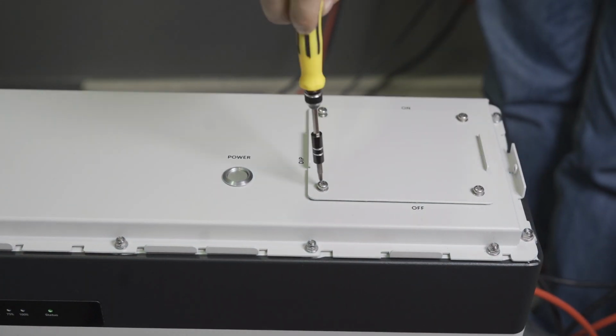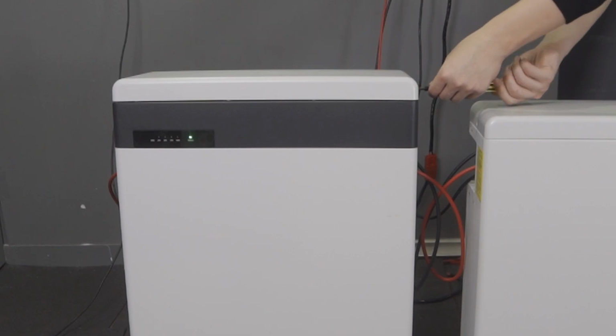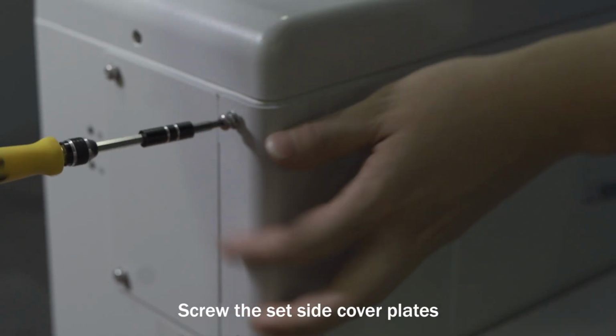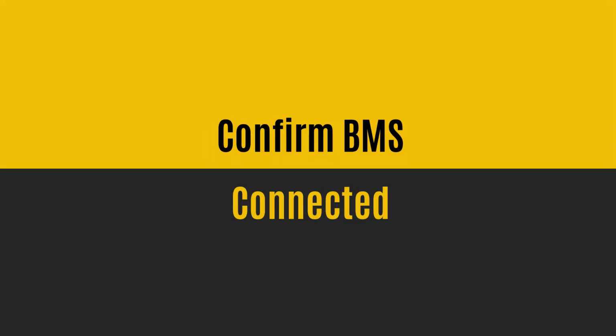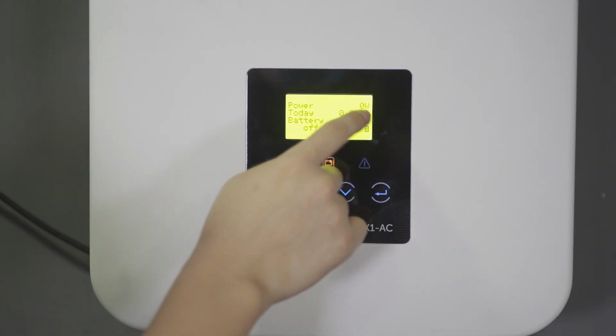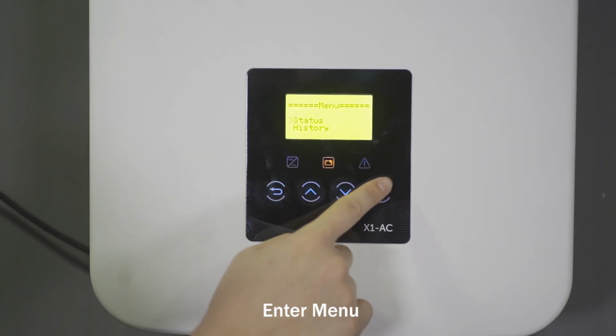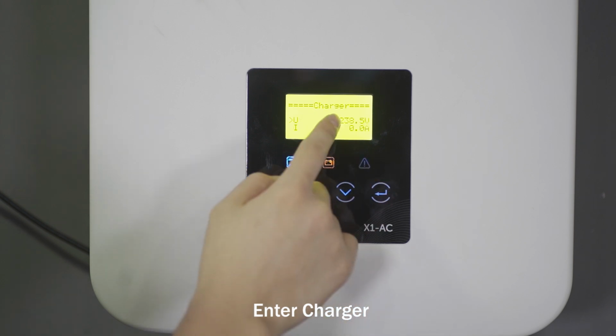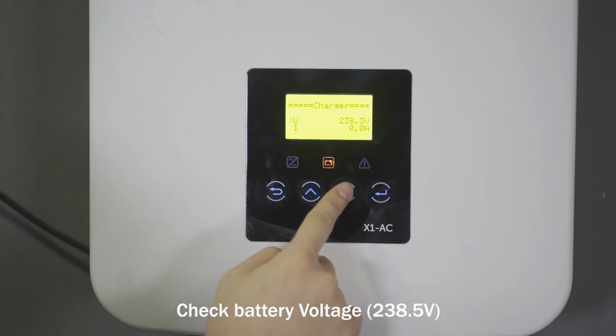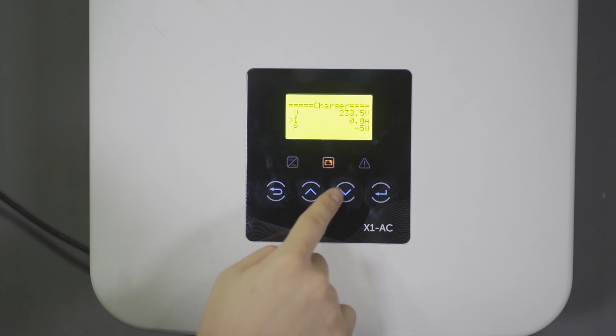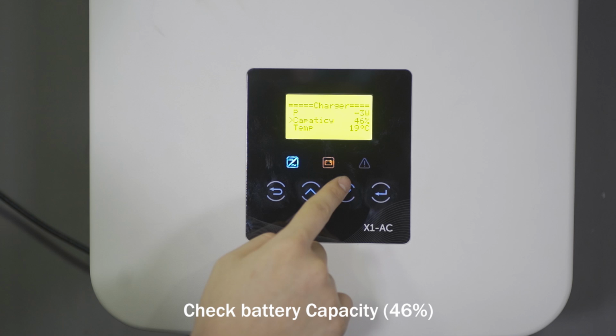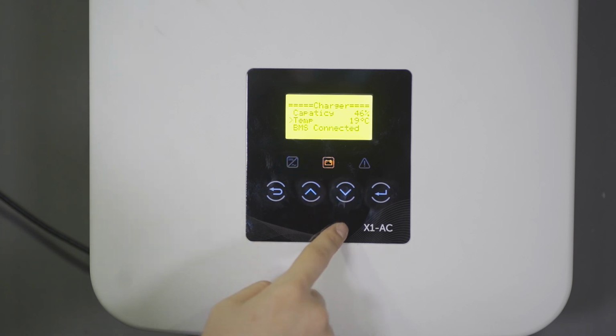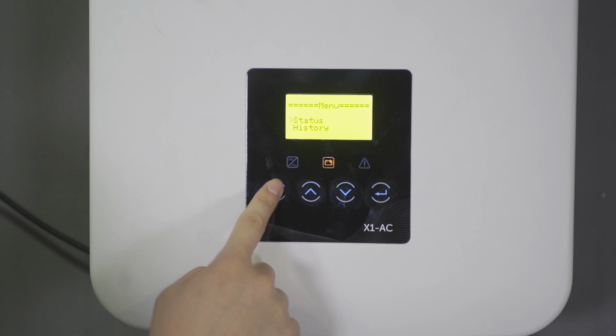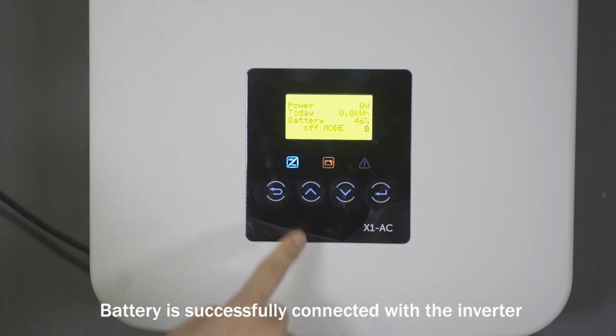Screw the small cover plate and the upper cover panel. Screw the set cover plates. Screw the set side cover plates. Enter menu, enter status, enter charger. Check battery voltage, 238.5 volts. Check battery capacity, 46%. Confirm BMS connected. Back to the main screen. Battery is successfully connected with the inverter.